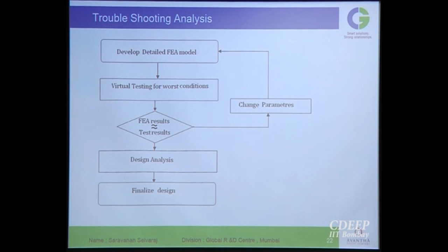This is one case study, of a multi-utility transformer. Actually, this transformer is connected to different utilities operating at different voltage levels. So it has a lot of copper bus bars which generate eddy currents, and this causes losses in the magnetic structure surrounding the bus bars. So they found very high hotspots, high temperature, in the magnetic structures. Because of that, the transformer did not clear the test and was not moving out of the factory.